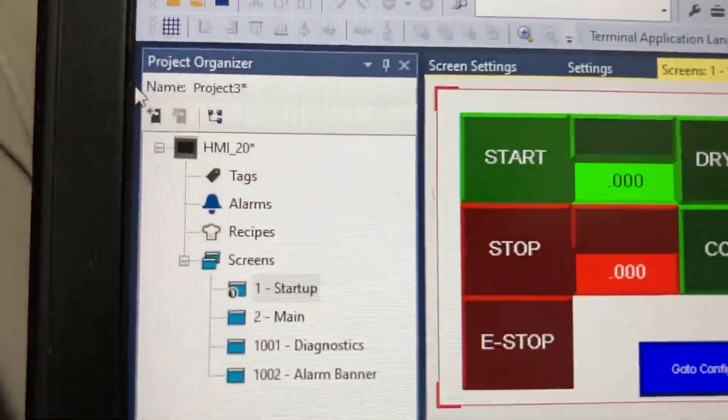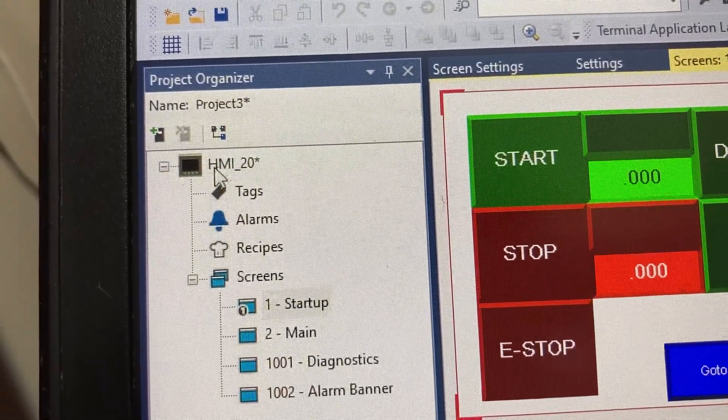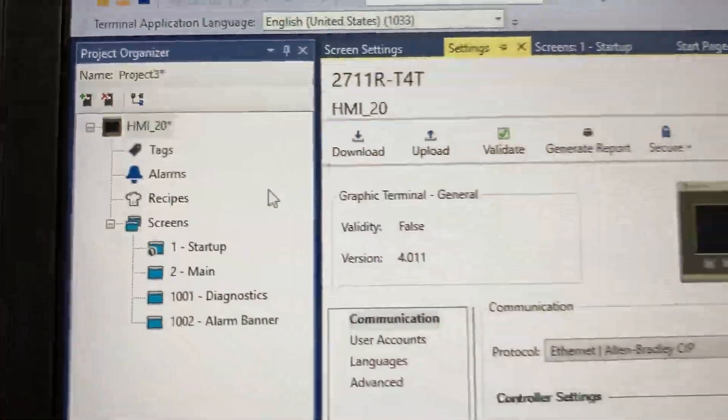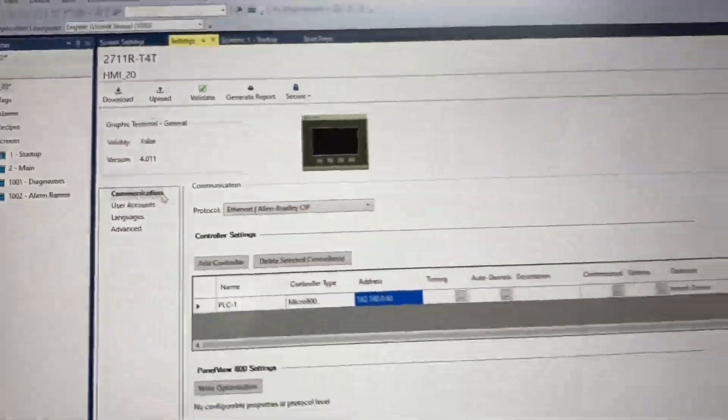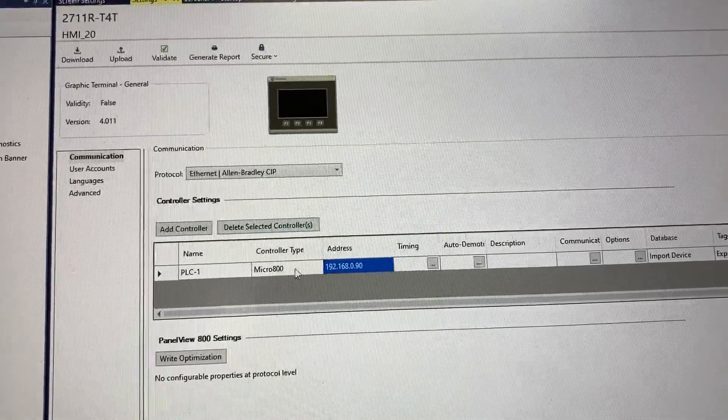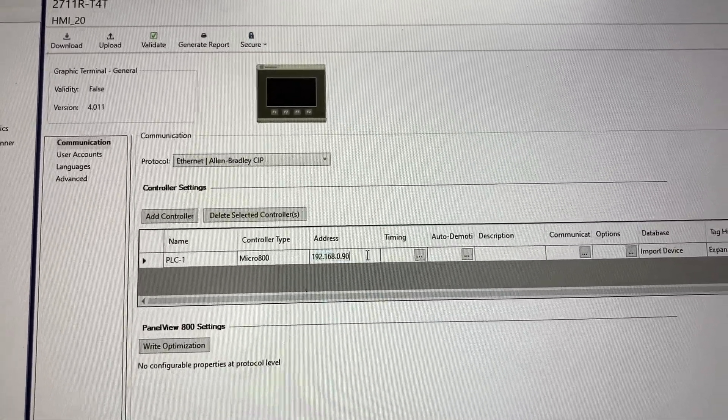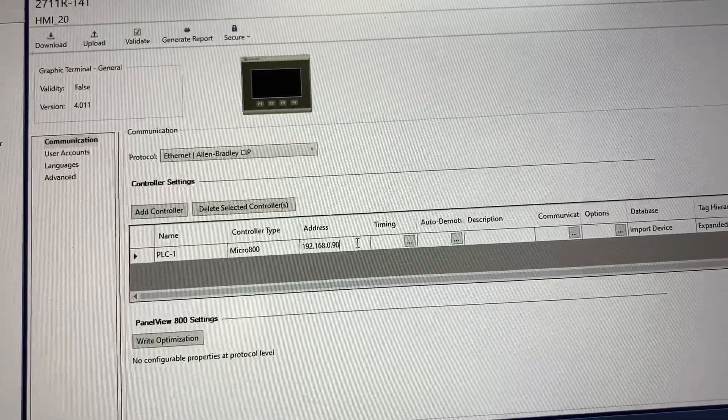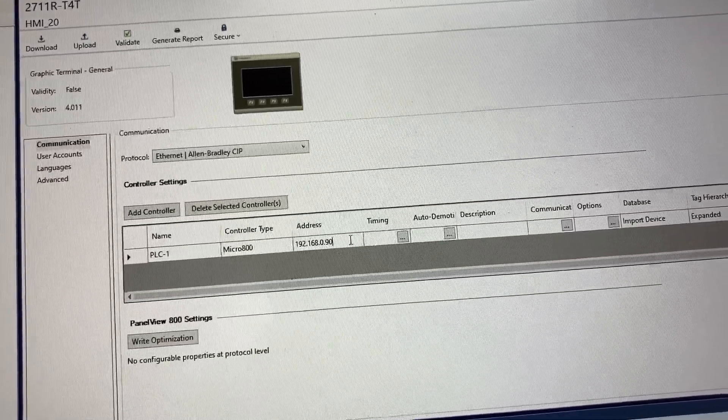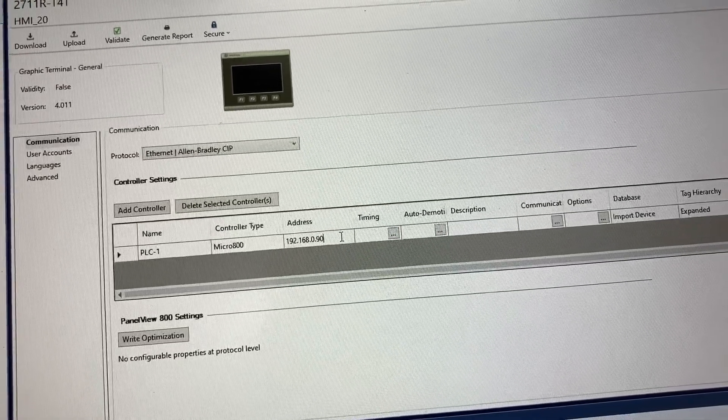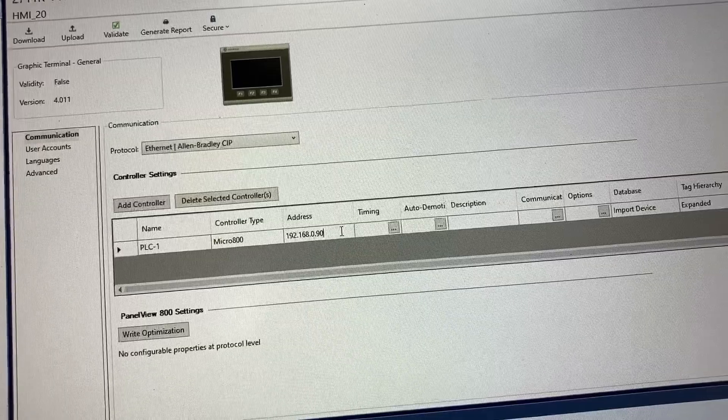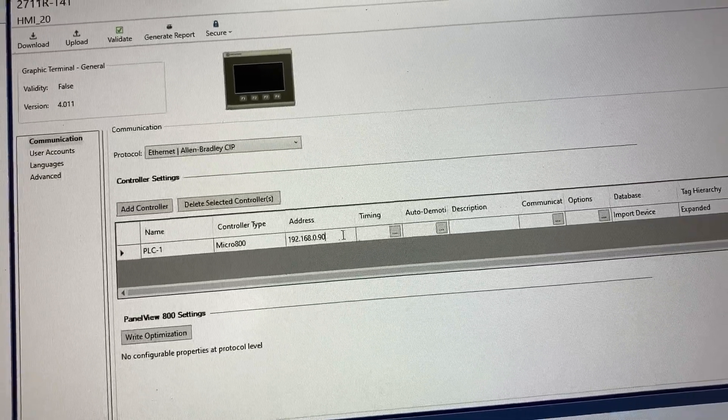Under Project Organizer, double click on the HMI. Then click on Communication. This is the current PLC IP address that the HMI is communicating to. So if the PLC IP address has been updated or changed, we need to update this in the HMI communication before it can see the PLC again.